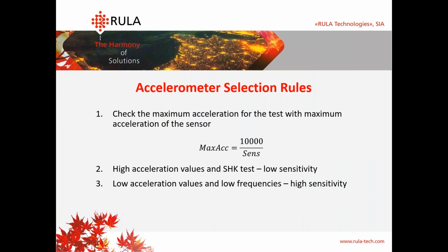It's very important to choose your sensors for the test really carefully. While choosing a sensor for the test, it's very important to know the frequency range and maximum acceleration value for the test. First of all, you know that our controller has the voltage limit of 10 volts or 10,000 millivolts. So you can find the maximum acceleration value, which can be got with your accelerometer. You need to divide 10,000 millivolts by your sensitivity. For example, if we have an accelerometer with sensitivity of 100 millivolts per G, the maximum acceleration value is 100 G.